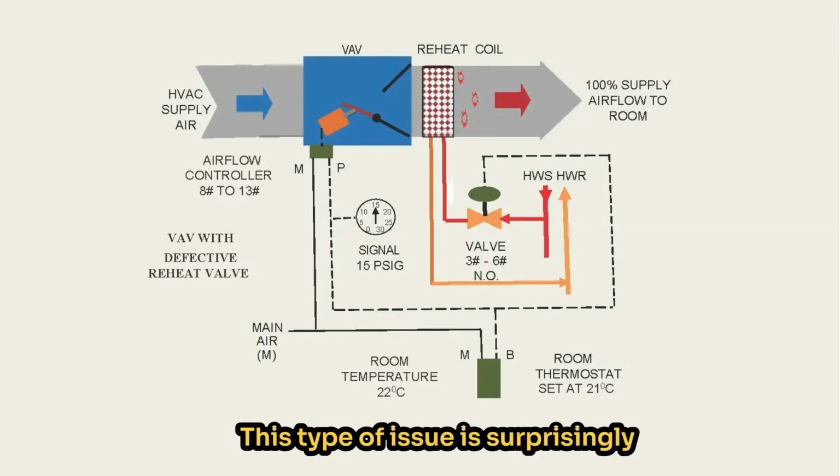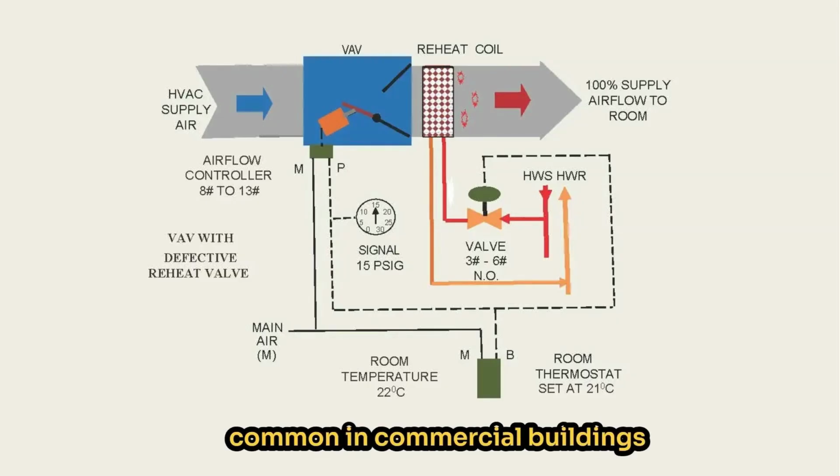This type of issue is surprisingly common in commercial buildings and often goes completely unnoticed because the temperature change may only be a degree or two, which occupants typically do not detect. However, the space is effectively being heated and cooled at the same time, resulting in significant and unnecessary energy waste.